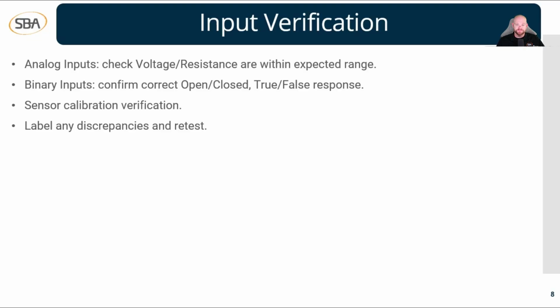Now, obviously, the thermometer and the actual sensor itself may not be calibrated to the same standard. So they could be different, but just know that if they are way off and you are getting a reading from your space temperature sensor, you may have to calibrate something or put an offset in the software in order to make up for that difference. But that's what this is saying when you're talking about sensor calibration verification. We're just verifying that the sensors are calibrated correctly and that they're reading how they should.